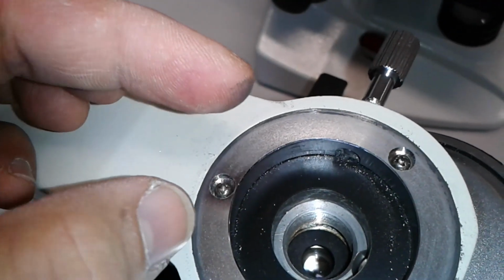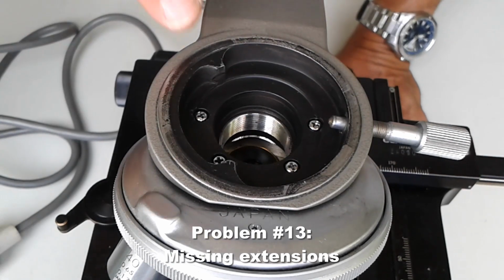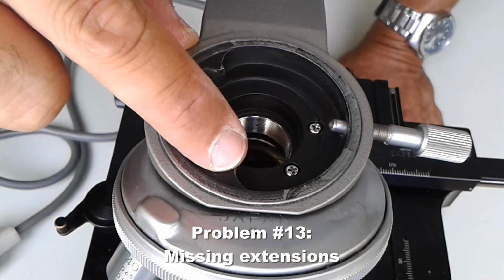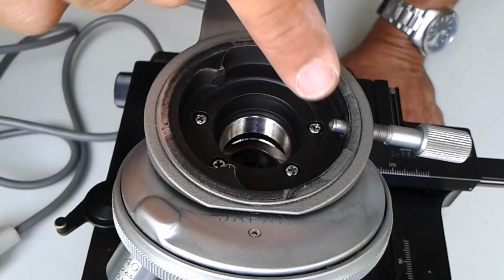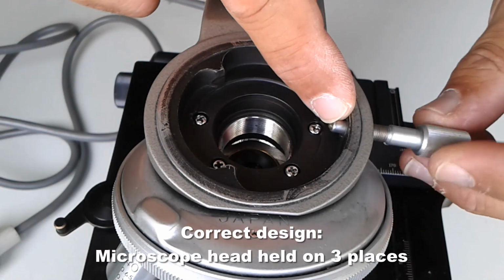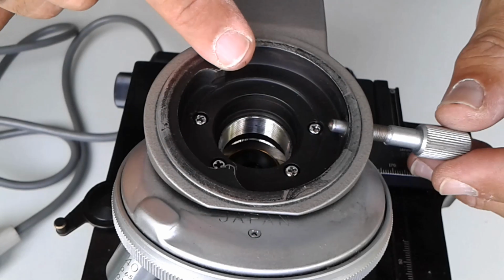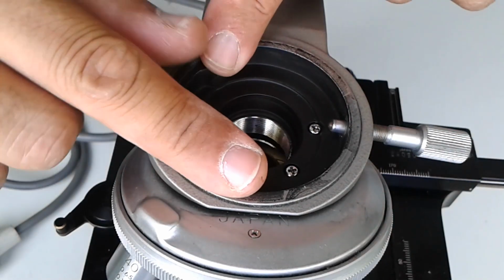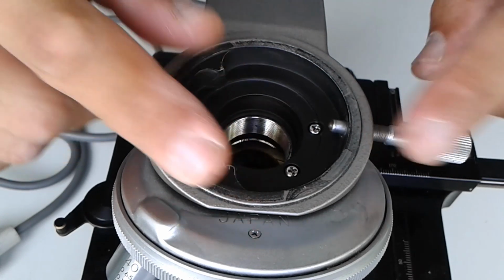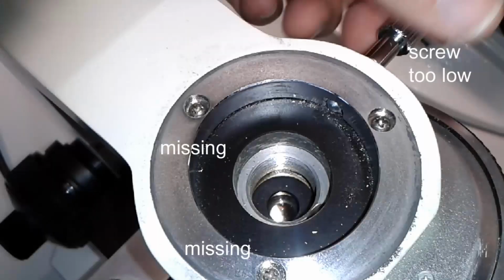And that's not good either, because those metal filings could actually drop into the objective. And a second problem is also that there was only this one screw, but in reality there should be 2 more places that hold the dovetail in place. And this is now the example of the quality microscope, where you can actually see that there are 2 more retainers that hold it in place, but they're missing in the low quality microscope. So the company who made this microscope actually did some shortcuts, but this completely defeated the purpose. I think this is even a safety issue, because the head actually drops off very easily.